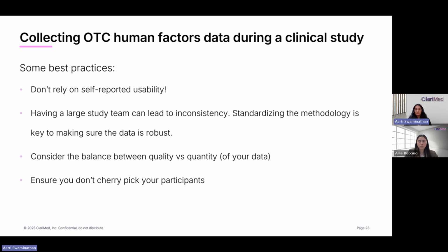The FDA puts a lot of emphasis on making that as representative as possible, including users who have lower educational or socioeconomic backgrounds. So make sure the participants you include aren't cherry picked to be higher level participants, people who are performing better, or people who lean towards any one demographic group and overrepresent that compared to what the United States Census might represent for that demographic subpopulation.